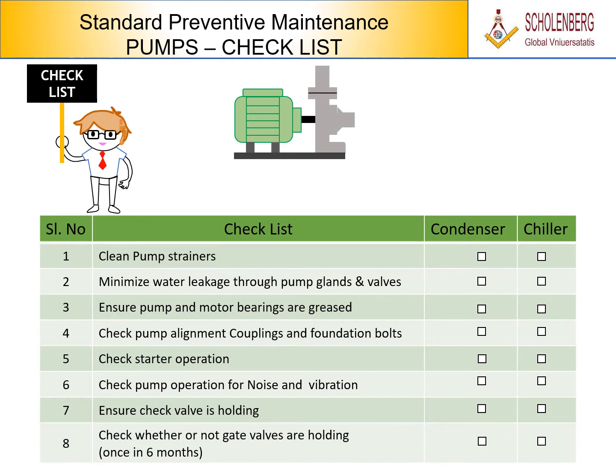Pumps, checklist. 1. Clean pump strainers. 2. Minimize water leakage through pump glands and valves. 3. Ensure pump and motor bearings are greased. 4. Check pump alignment, couplings and foundation bolts. 5. Check starter operation. 6. Check pump operation for noise and vibration. 7. Ensure check valve is holding. 8. Check whether or not gate valves are holding. Once in 6 months.